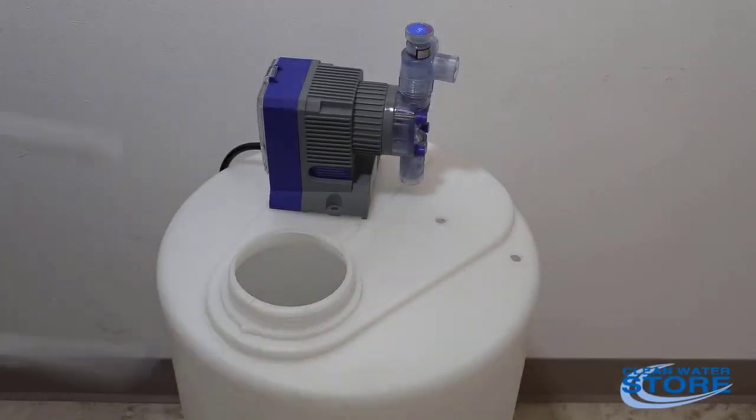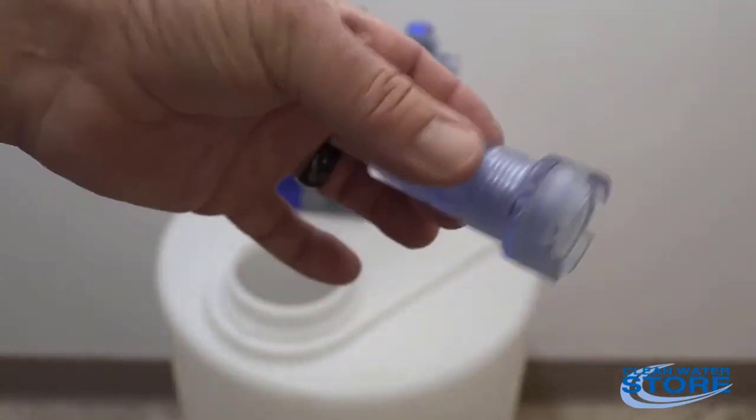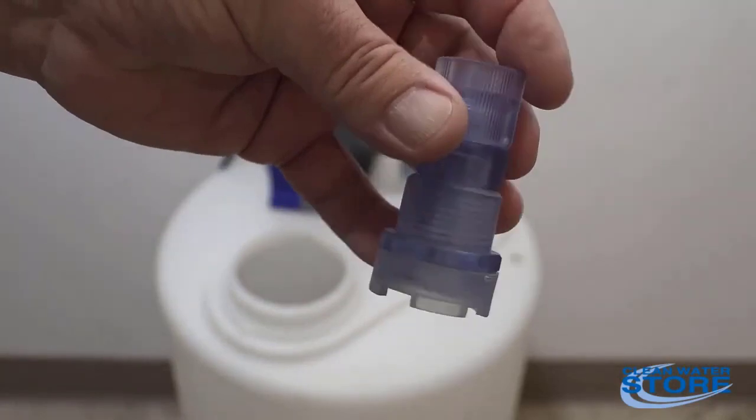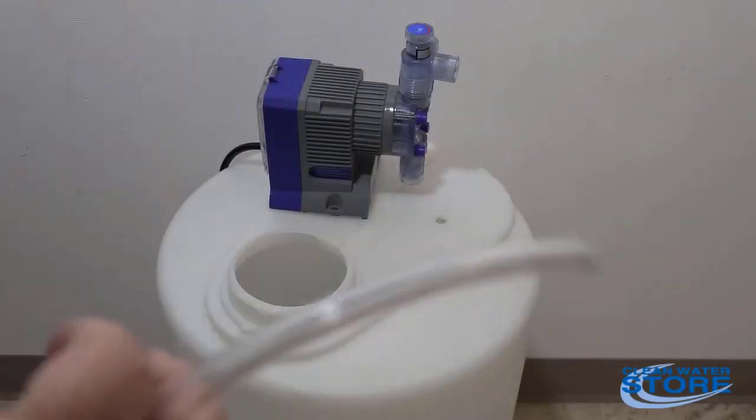Another important thing is that you want to make sure this is vertical. This foot valve has a check valve in here, and if it's off horizontal or to the side, it could not function properly and you won't keep your prime on the pump. So make sure this is vertical and use your soft tubing.